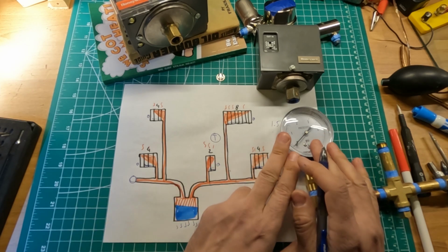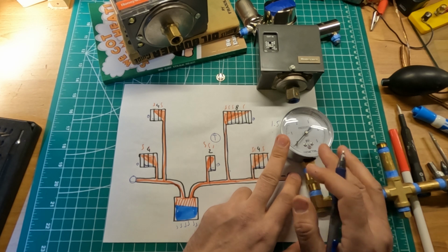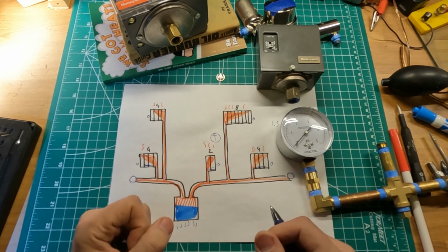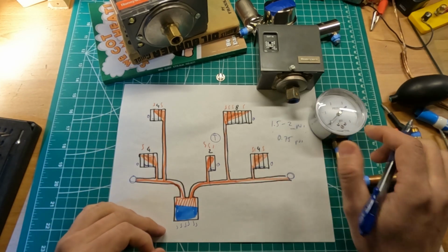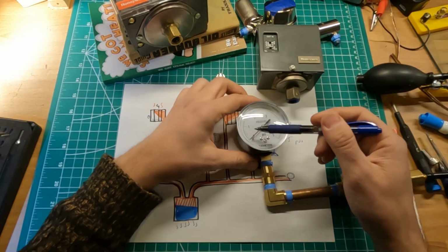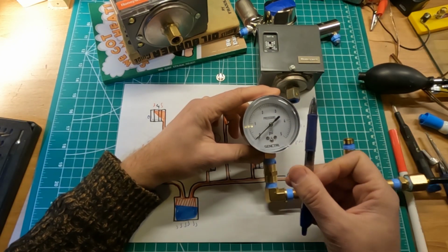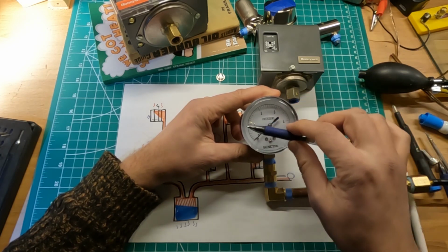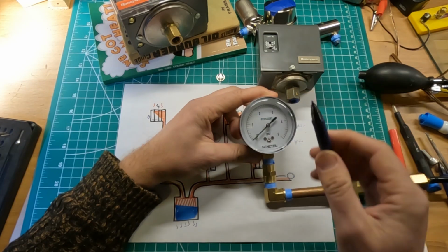That's one of the reasons it's great to have a low pressure gauge attached to your boiler, so that you can actually see things happening in your system as they happen, and react to it. So anyway, let's say you've seen the system building up from 0 to probably 1 psi, 1.5 psi. It takes say 3, 4, 5 minutes. And then when the boiler shuts down at 1.5 psi, you should see quite a rapid drop to 0.